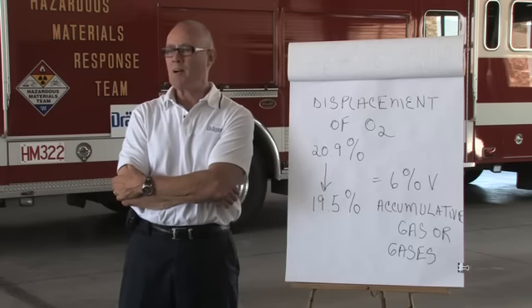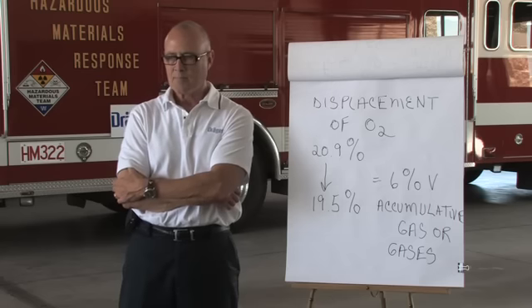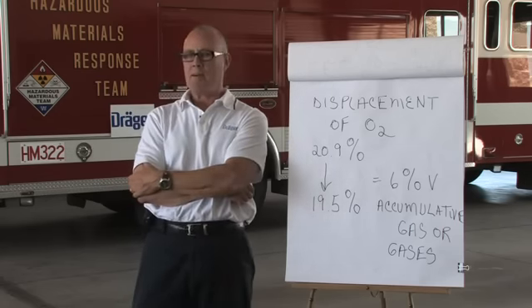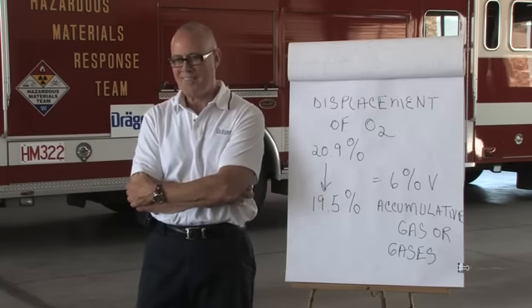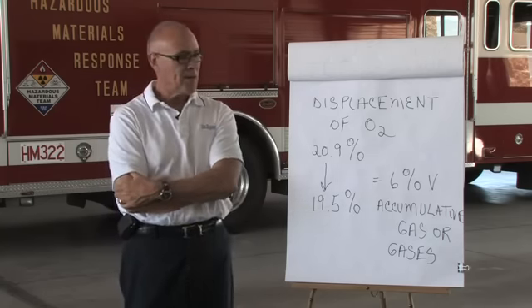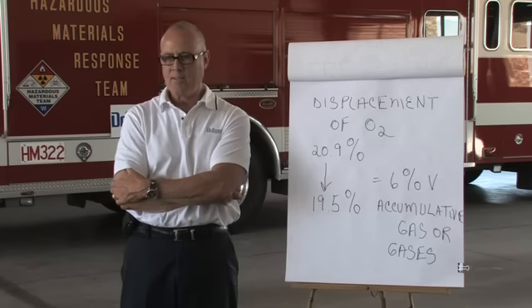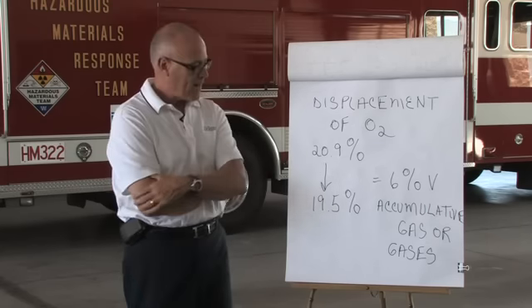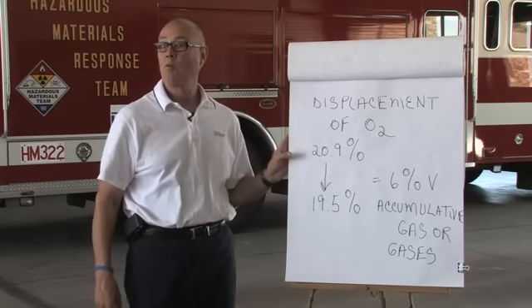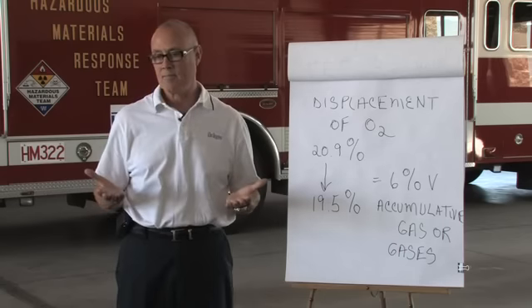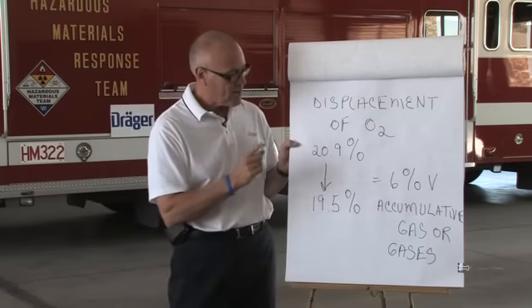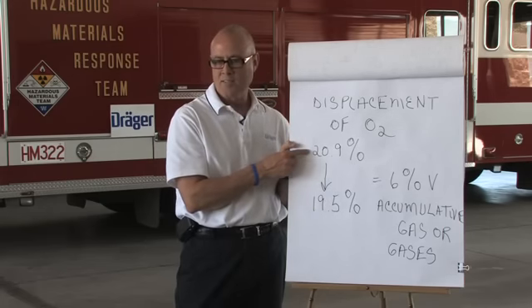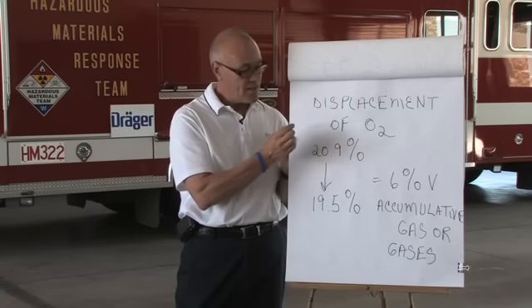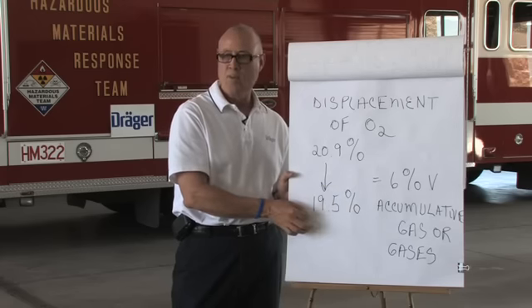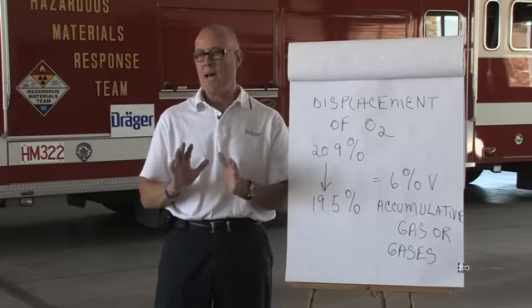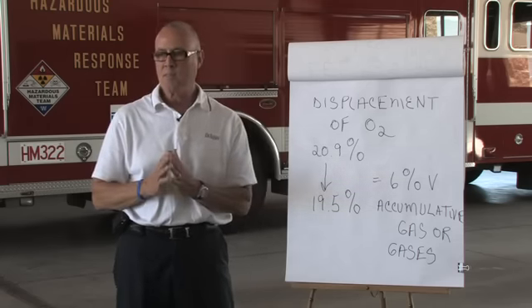And that's if you're basically turning the meter on in the same neighborhood all the time. But if we leave here today and head up to Big Bear, or I should say Arrowhead for you guys, what's going to happen when you get up there is you're going to turn your instrument on and your oxygen readout is going to be lower. It's going to be down at maybe 20.2, 20.3, 20.4. And when you turn it on, that's an unacceptable start point. You've always got to start with a 20.9% on oxygen, always. And you always have to start at 0 LEL, 0 CO, 0 on H2S. If any of those numbers are not on those markers that I just called off, then something's not right.